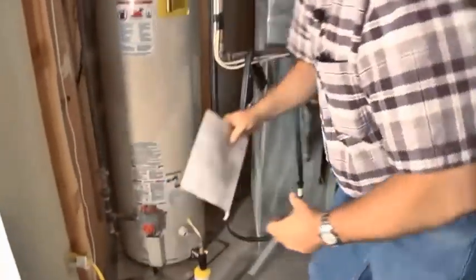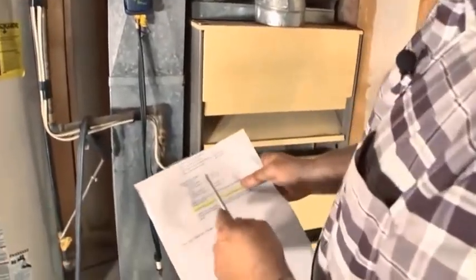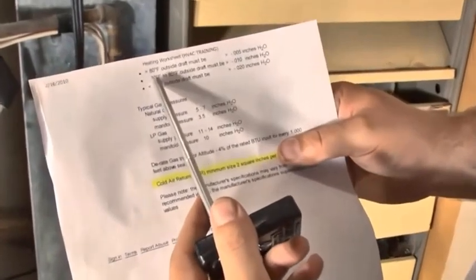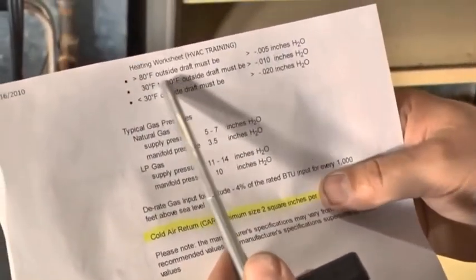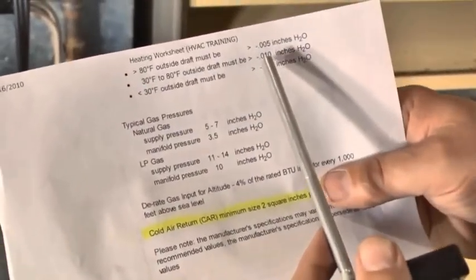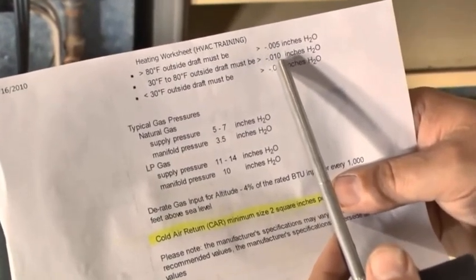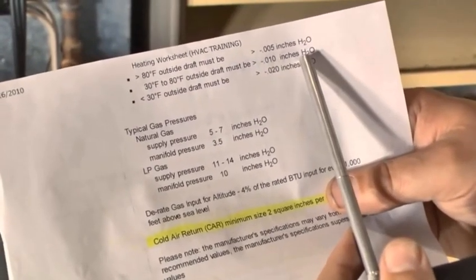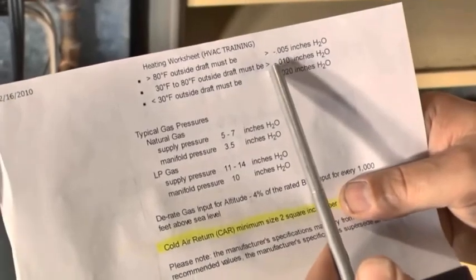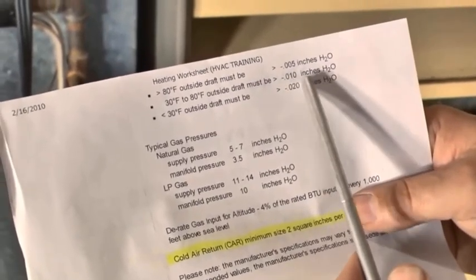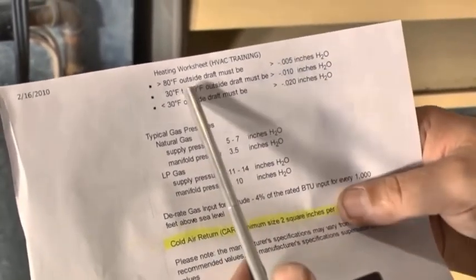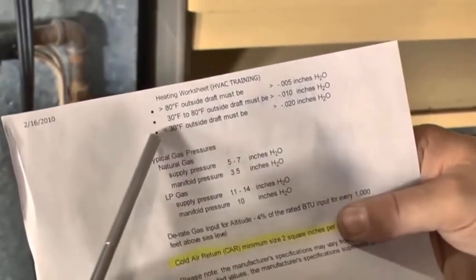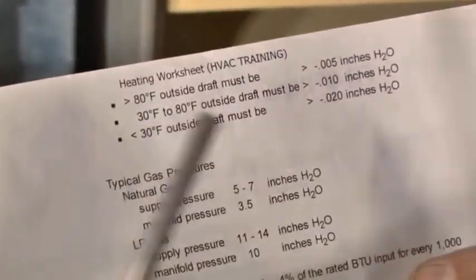column. Okay, out, and then I use my chart here. I have a chart here that tells me I'm about 60 degrees outside, so between 30 and 80, so I'm in that range. I need to have greater than minus 0.01 inches of water column, H2O, and I have minus 0.02, so I have adequate draft for this temperature. It varies with temperature. The threshold varies with temperature.